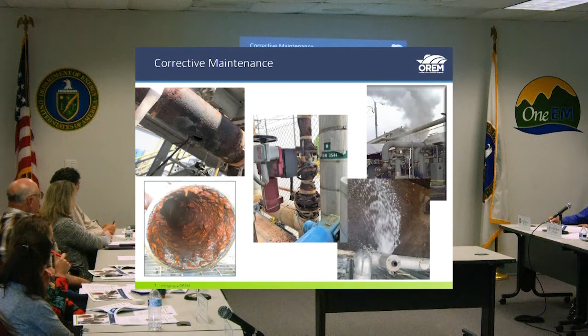So here's some photos. Kind of hard to see with the lights on in here, but this photo shows that every time we take heat tracing off of pipes, we find this kind of thing. You can see all the rust and corrosion here on these systems that cause us to have to go in and replace pipes, and so that's been more and more frequent. This shows some of the internals of a pipe that came out of the clarifier, I think, or bottom of the clarifier, with corrosion and buildup of corrosion products on the inside of the pipe. Basically, this was a pretty good leak. And most leaks aren't nearly that major, but this was a major one that pipe broke from corrosion problems.